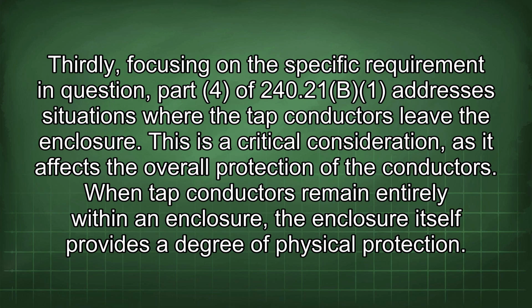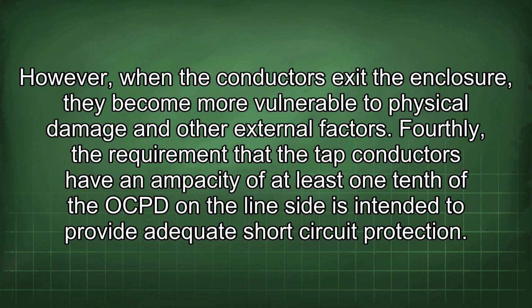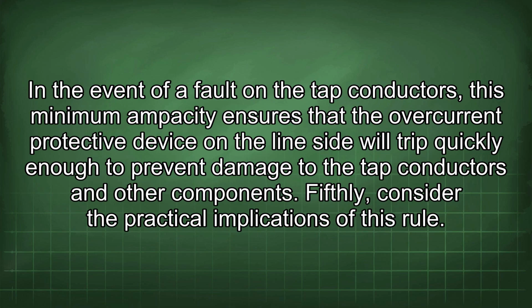When tap conductors remain entirely within an enclosure, the enclosure itself provides a degree of physical protection. However, when the conductors exit the enclosure, they become more vulnerable to physical damage and other external factors. Fourthly, the requirement that the tap conductors have an ampacity of at least 1/10 of the OCPD on the line side is intended to provide adequate short-circuit protection. In the event of a fault on the tap conductors, this minimum ampacity ensures that the overcurrent protective device on the line side will trip quickly enough to prevent damage to the tap conductors and other components.